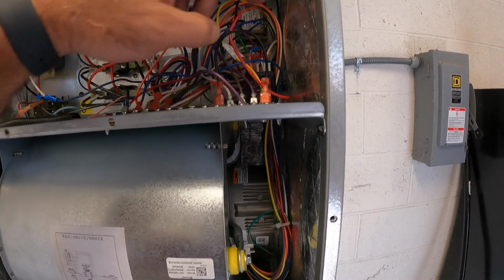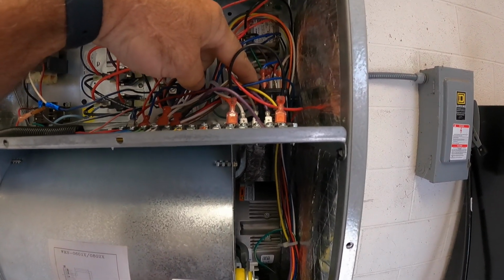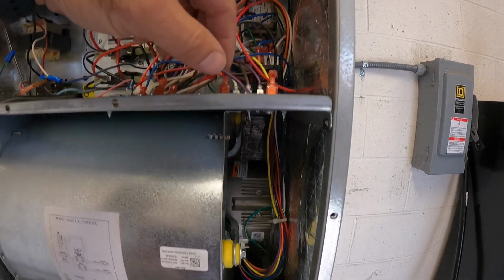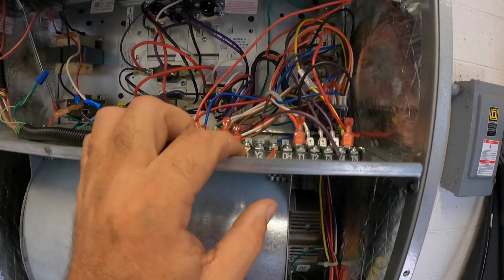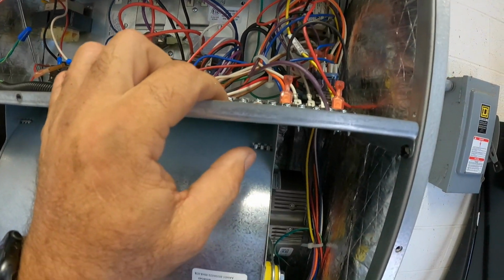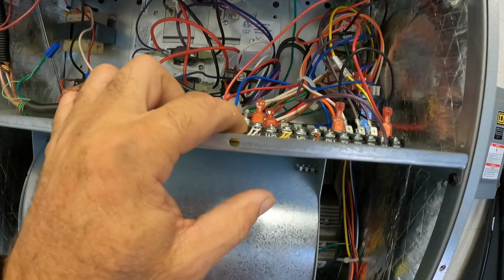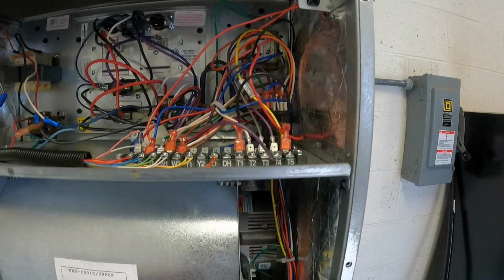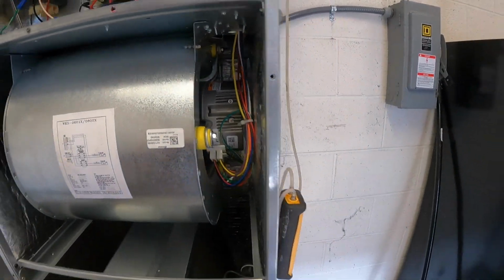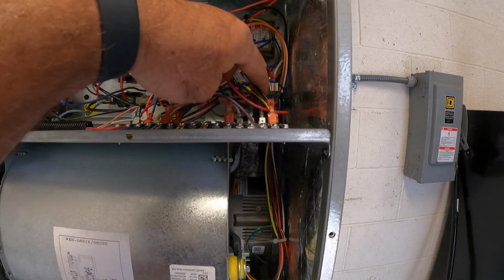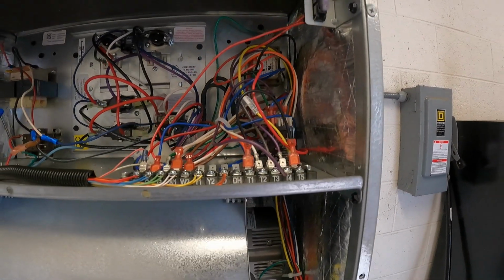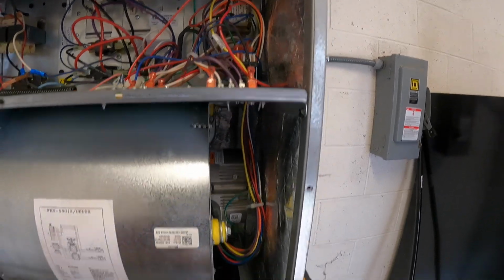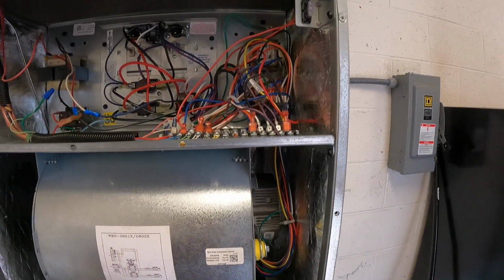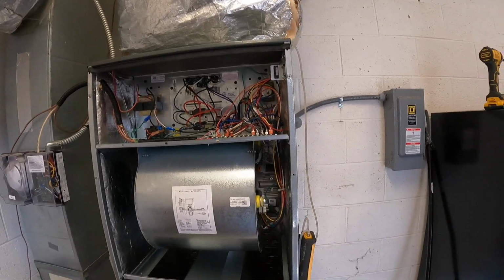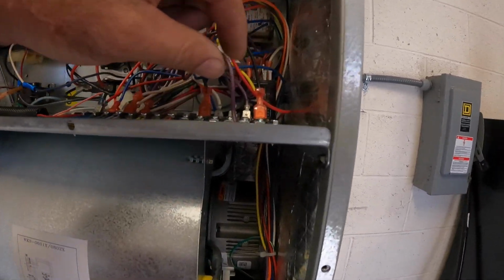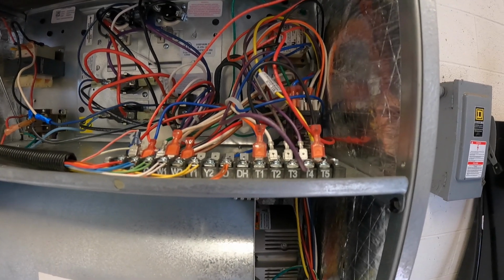In fact, if it were mine, I would probably do away with this relay entirely and just run my speed taps off of either my compressor or my electric heat or my fan. And you could do that easily with this system. You just have to do a little rewiring on it. So I think someday when these relays start failing, there'll probably be a lot of people that just eliminate them out in the field and go straight to making it hit the motor for the actual speeds that it wants. But for now, I'm going to move this purple wire down to T2 and we'll turn it back on and do another test.